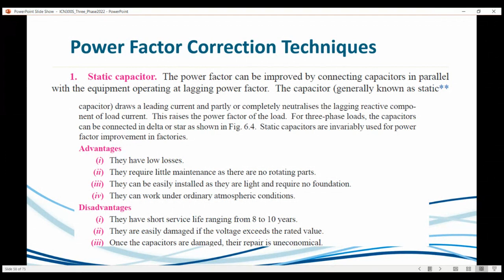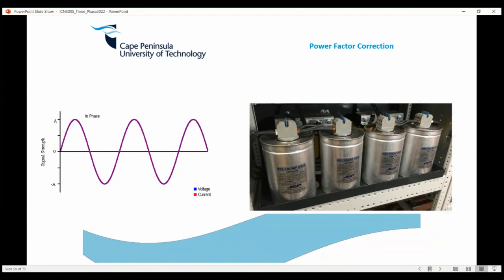So that's what a typical capacitor bank looks like. This is at the supply where they put it up. They put these four capacitors in, or I'm not sure exactly, there's a capacitor bank, each to correct the power factor. But the graph I want to show you is this: first there's an inductive load which pushes the current out of phase with the voltage, and then power factor correction brings it back. When we apply the capacitor banks, it pushes it back again. It's basically trying to make the current sine wave completely in phase with the voltage sine wave. Okay.